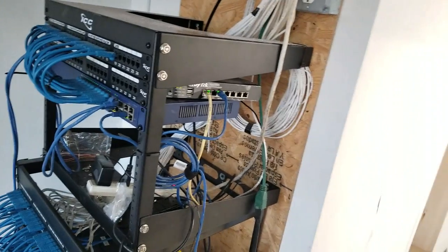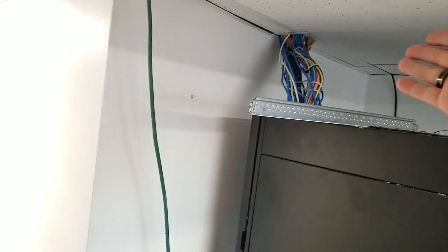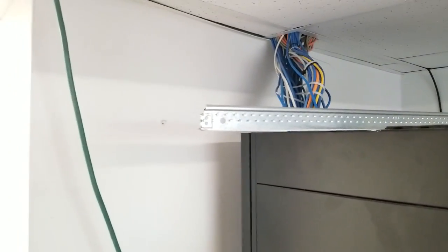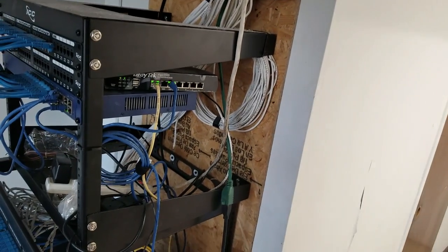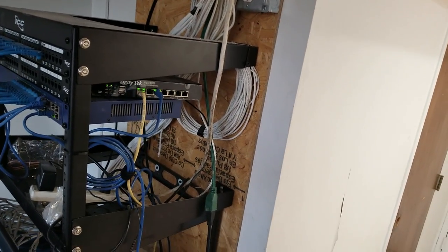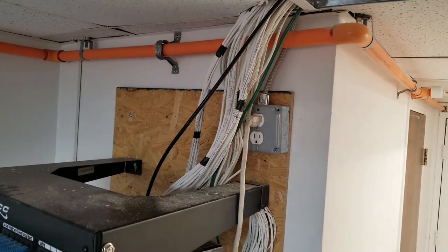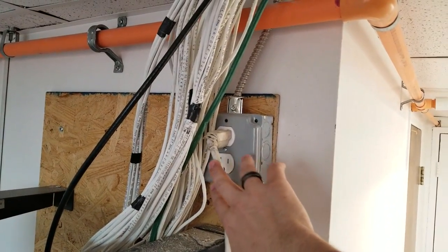Unfortunately all of this is keeping their data and systems up and running. They've got servers in that APC data closet — luckily I'm not touching that wiring. And wow — there's another extension cord. Which is strange because they already have power there, so why bring in a second one? Maybe they added it and didn't want to unplug the first. That's definitely a fire hazard. And this wiring over here — it's coming apart too. Good lord.